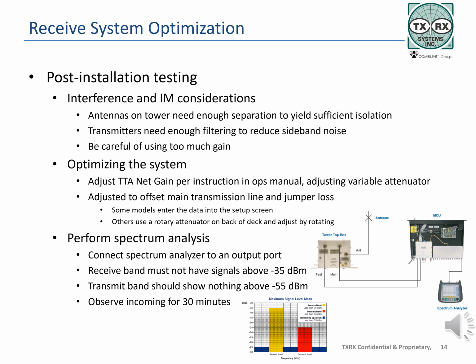Enough gain should be used to offset any transmission line losses, while using enough gain to give the system optimum sensitivity. Amplifier gain may be adjusted manually or with digital attenuators. Newer models will use auto setup, with the technician entering site data and the unit setting itself up.